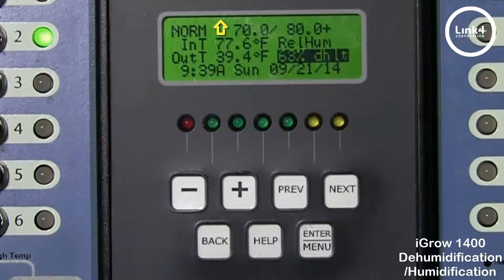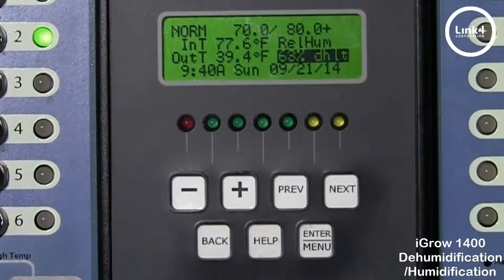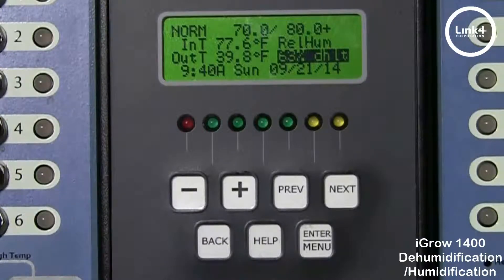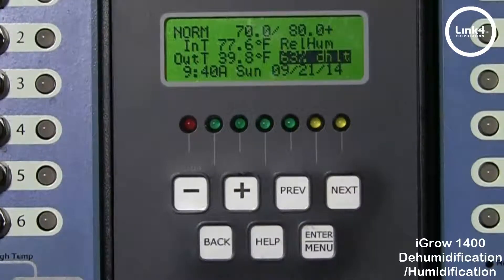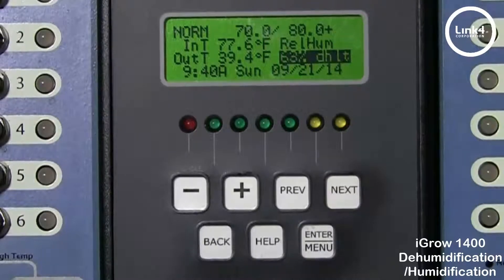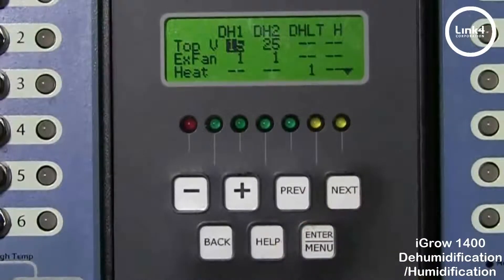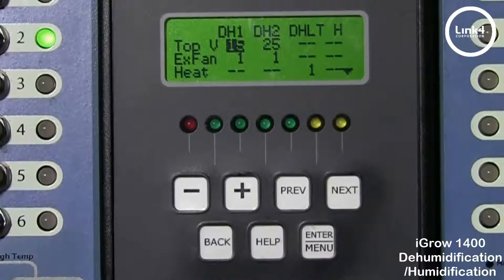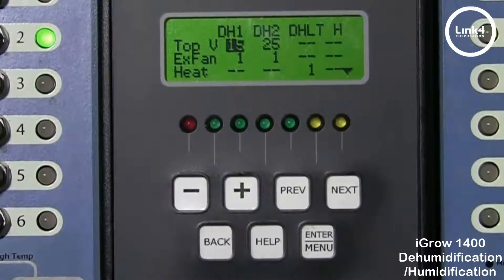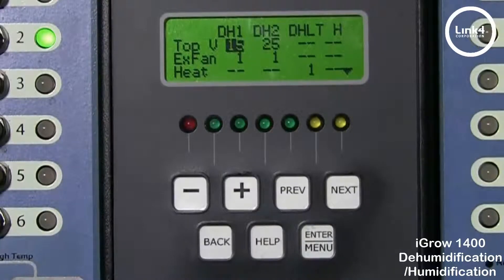In this final view, the outdoor temperature is 39.4°F. The threshold for DHLT to come into effect is 40 degrees, and the relative humidity is above the high humidity setpoint, which makes the controller go into DHLT. Now that you have a basic understanding of how dehumidification and humidification works, we encourage you to use these options to cycle and control your humidity levels within your greenhouse to best suit your needs. That's our video on programming dehumidification and humidification with your equipment.